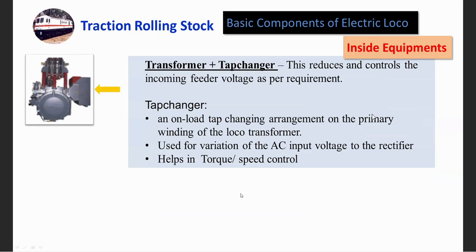These are all DC traction motors, and we need to change the incoming voltage to the DC traction motor as per the requirement of torque or speed. The 750 volts is the upper limit, and there is a possibility we may need to supply a voltage less than 750 volts to the traction motors. This function is performed by the tap changer.